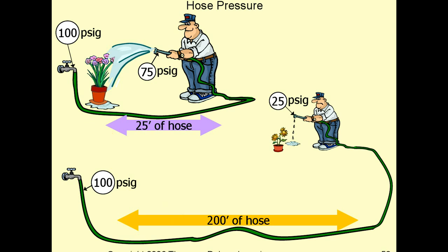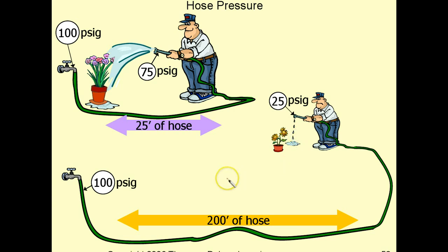Here's a great example of how a cap tube works — it's just like your garden hose. If you have 100 PSI of pressure coming out of your spigot and 25 feet of hose, you'll have 75 PSI of water coming out the end of the hose because the friction of the hose drops the pressure. Now take that same spigot at 100 PSI and put on 200 feet of hose — you hardly have any water coming out. This is the same principle as a cap tube.